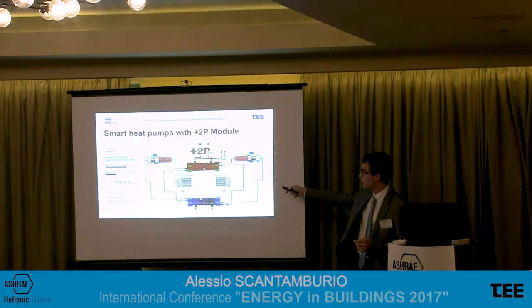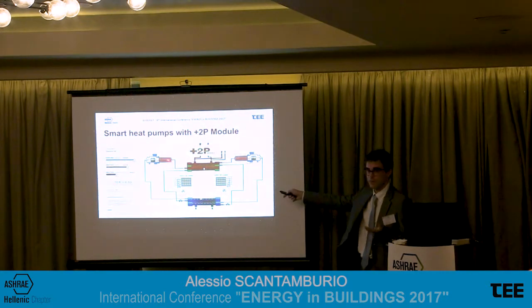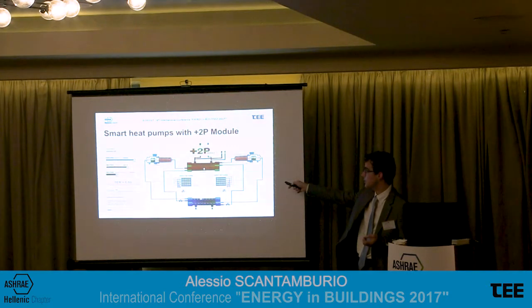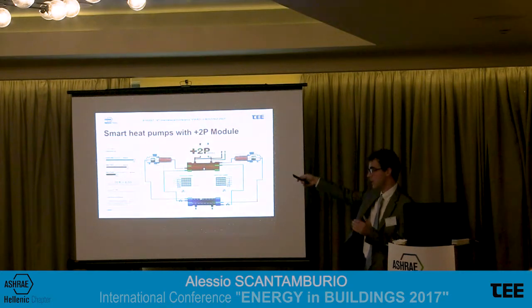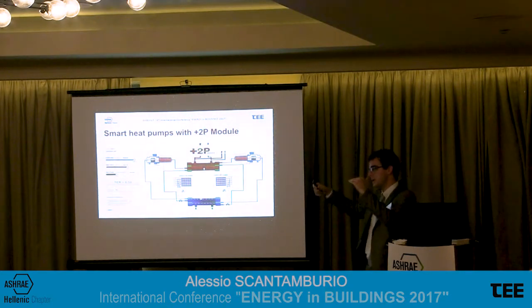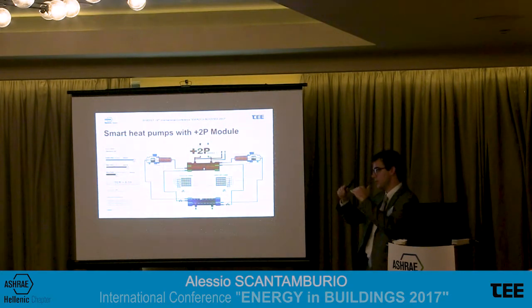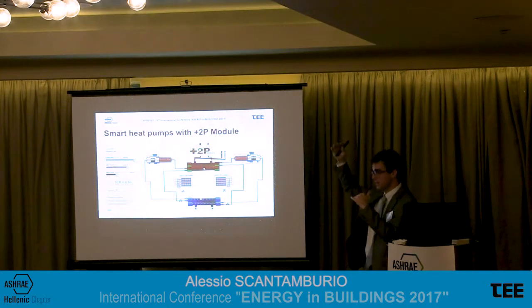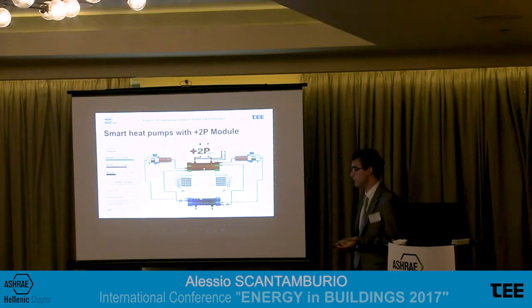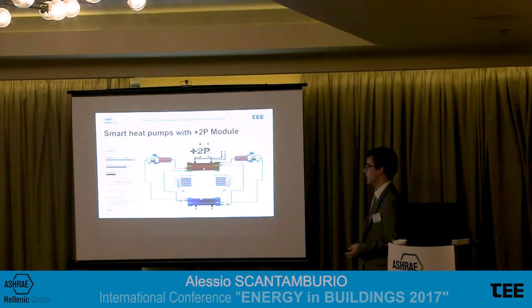It takes part of the medium temperature hot water produced by the smart heat pump, the 4-pipe unit. Here we can have 45 degrees, for example. This 45 degrees hot water is sent to the evaporator of this additional water-to-water heat pump. And so by evaporating higher, thanks to special technology inside, we are able to condense higher, and so to produce 78 degrees of hot water.